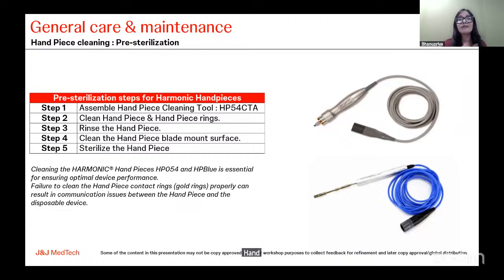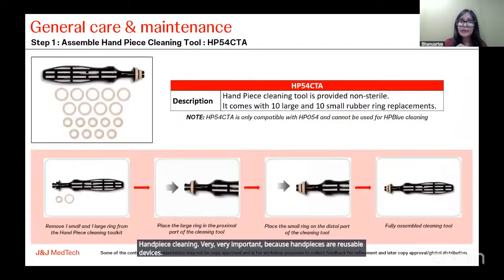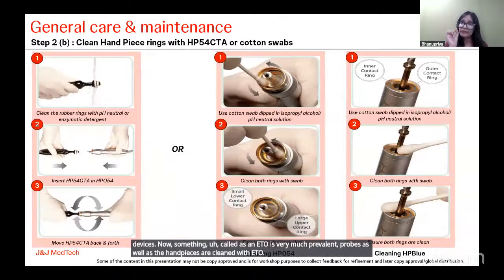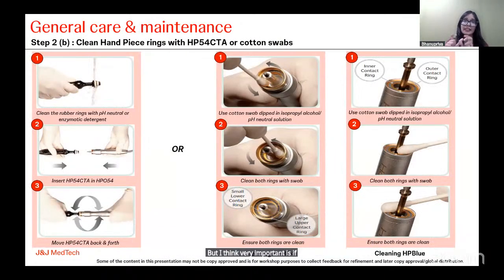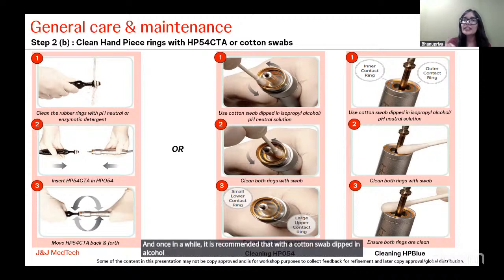Handpiece cleaning is very, very important, because handpieces are reusable devices. Now, something called ETO is very much prevalent. Probes as well as the handpieces are cleaned with ETO. But I think what is very important is, if you look at a handpiece in depth, you'll find that handpieces have two golden rings inside of them, both the open handpiece as well as the laparoscopic handpiece. And once in a while, it is recommended that with a cotton swab dipped in alcohol, both these golden rings be cleaned adequately.